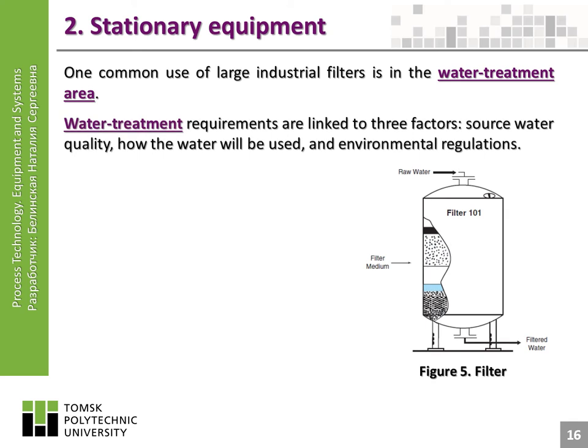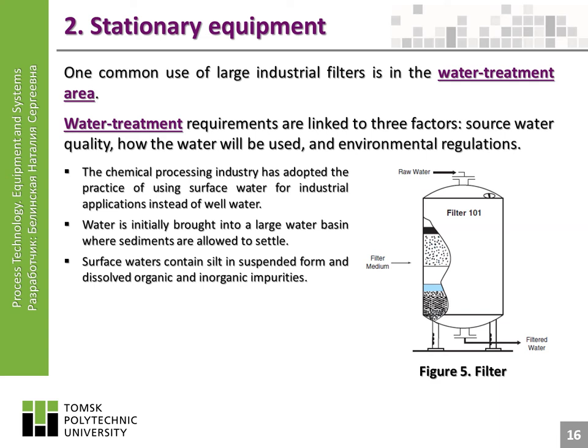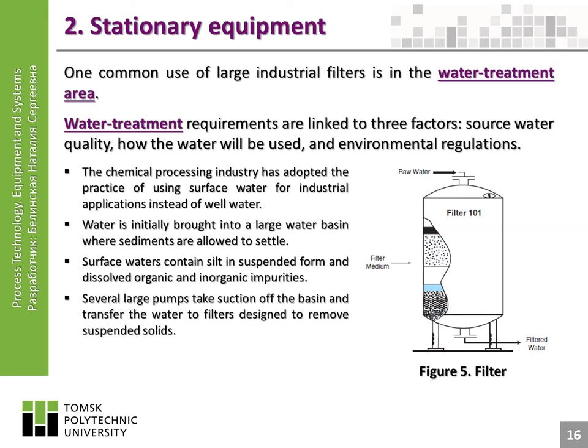One common use of large industrial filters is in water treatment. Water treatment requirements are linked to three factors: source water quality, how the water will be used, and environmental regulations. The chemical processing industry uses surface water for industrial applications. Water is initially brought into a large water basin where sediments settle, and surface waters contain silt in suspended form and dissolved organic and inorganic impurities. Several large pumps take suction off the basin and transfer the water to filters designed to remove suspended solids.